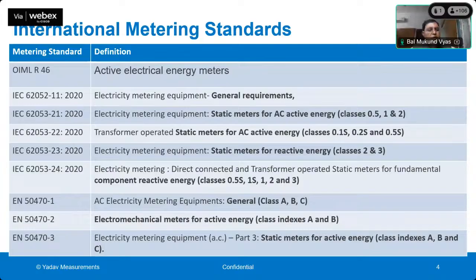electricity meters. Then there are various IEC standards. IEC TC13 makes the standards for electricity meters, and they have these 5 types of standards. In fact, there is one more standard, 62052-11. It gives you general requirements, and then 53-21 gives you particular requirements for class 0.5, 1 and 2. 22 is for class 0.1S, 0.2S, 0.5S. So you can see there are standards up to 0.1 accuracy.